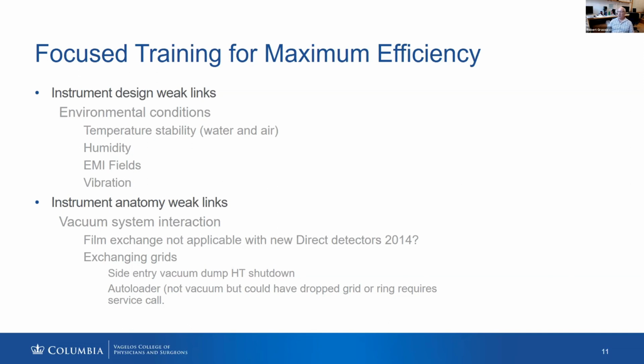The second weak point of the vacuum interaction is the exchanging of the grids. With the side entry holders, you can dump the vacuum if you're not careful. A lot of these newer holders, like the ELSA holder that has a very heavy door, can cause uneven pressure on the O-rings going into the microscope, which can cause the vacuum to dump if you don't support it properly. With the autoloader, that's not as much of a problem, but of course you need to be careful not to do something to cause a problem. So automation helped with that.